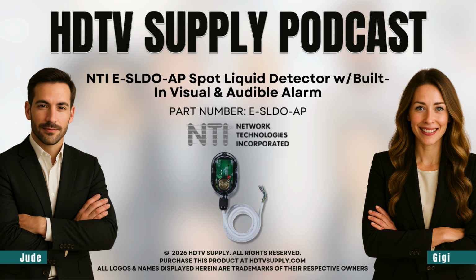But why that level of microscopic detection? Isn't 0.03 inches just overkill? You'd think so, but if we connect this to the bigger picture, it's all about prevention, not reaction. When you're dealing with high-voltage switchgear, you cannot wait for a puddle. Detection at that level means you're catching the very first signs of, say, condensation, before it can get drawn into the electronics. Precisely, before capillary action can pull that fluid where it can do catastrophic damage. If you wait for a drip, you've already lost.